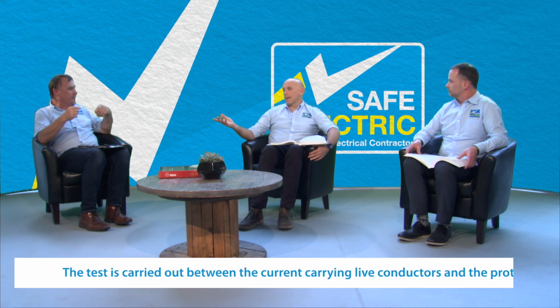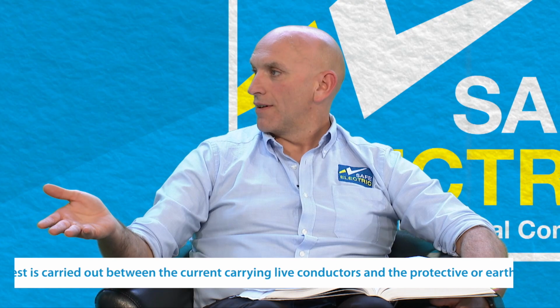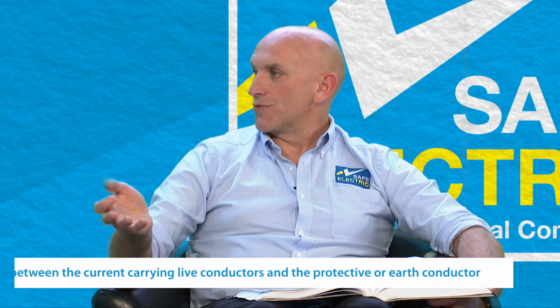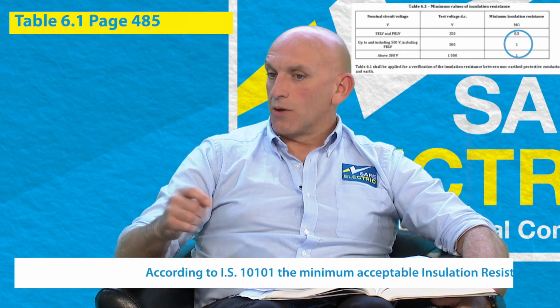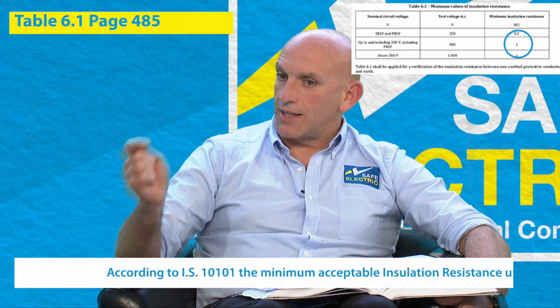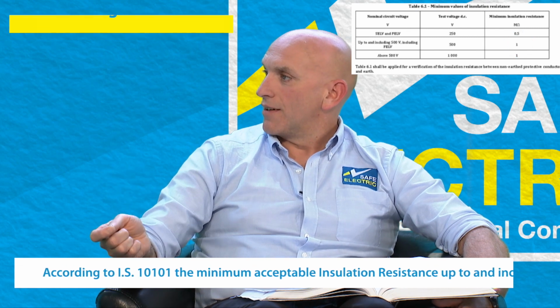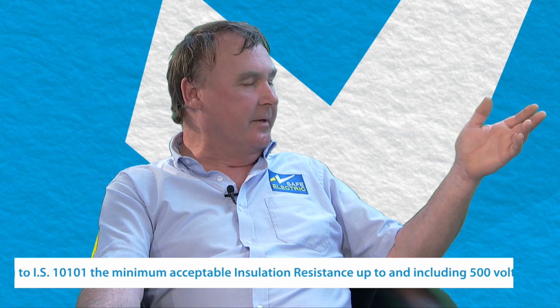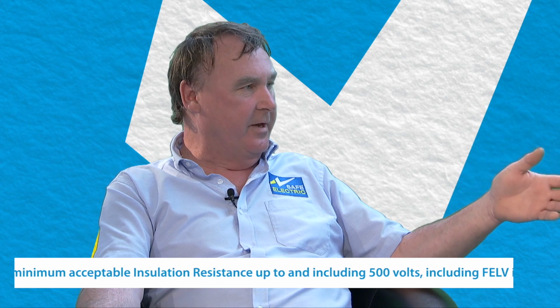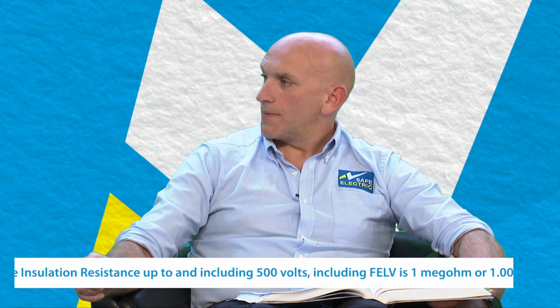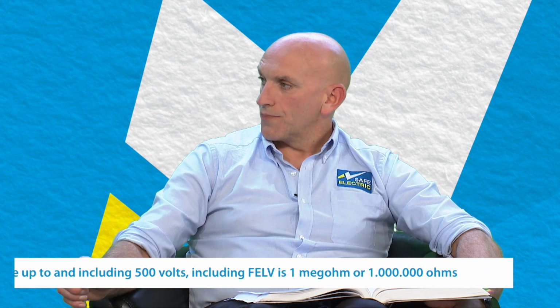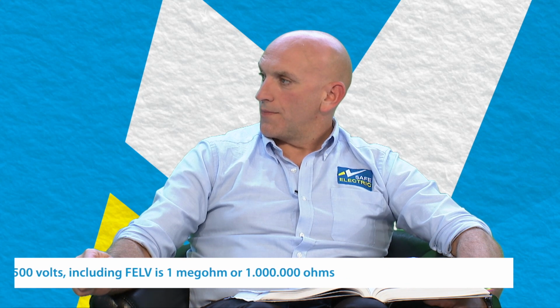I suppose one of the main parts of the certificate is the requirement for the minimum insulation resistance value of the entire electrical installation. Yes. So you can achieve this then by all of your MCBs switched on, or if you've got greater than 50 circuits, you can achieve this by using an equation again, adding up your minimum insulation resistance values. But that reading needs to be achieved. And would you agree that the best test to verify this is to do at the end of the job, almost the last test you do, an overall live and neutral insulation resistance test to earth?